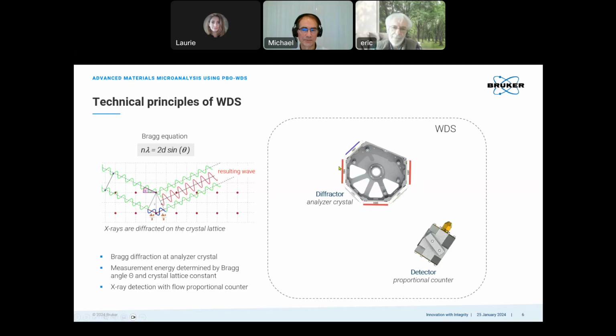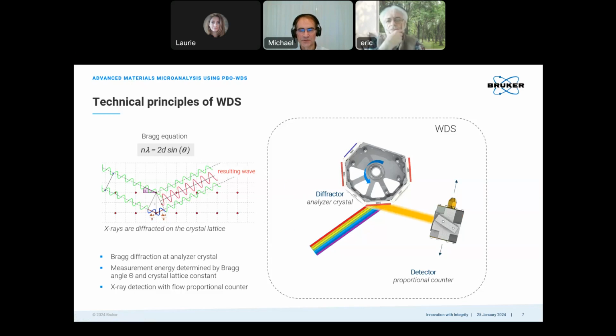The core part of any WDS is the diffractor system. Using crystals or multilayer elements, we offer up to 6 crystals covering the entire energy range that can be analyzed. And these analyzer crystals act as monochromators. So from a polychromatic X-ray beam, they filter out and intensify one certain energy, one wavelength, and this wavelength of X-rays is then reflected towards the detector, which is simply a counter, just counting the intensities. And what energy is detected here depends on the theta angle, and with a changing angle, we reflect a different energy towards the detector.